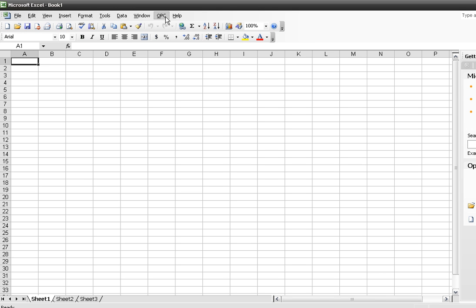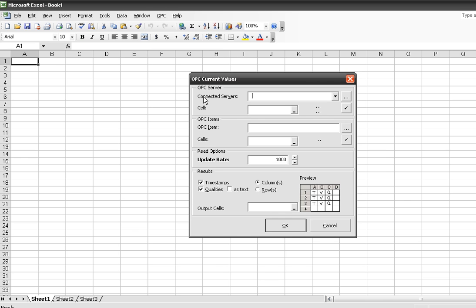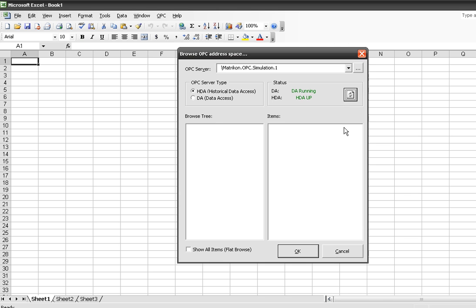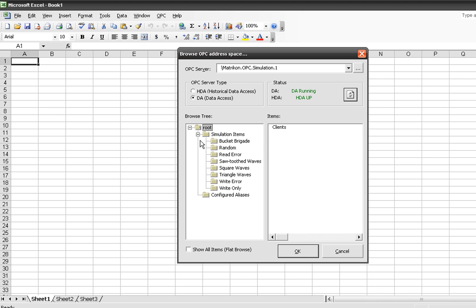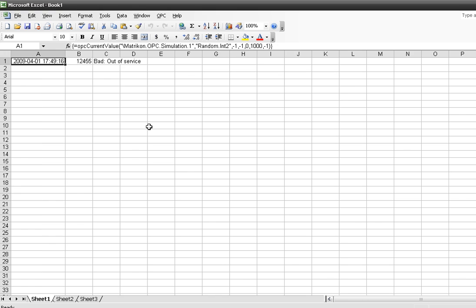The OPC toolbar is available up here. I want to read out some current values. I'll connect and grab data out of simulation. Here's the nice part — I get to browse for the tags, so I don't have to mess around with tag syntaxes. Update rate of 1,000. I'll take qualities as text, because OPC qualities when not decoded are just numbers, and I'd rather see them as text. After a brief moment, it pops to good and I start getting data, and it's updating.